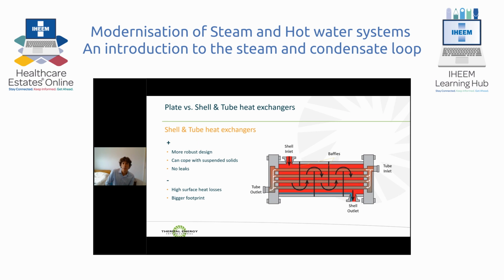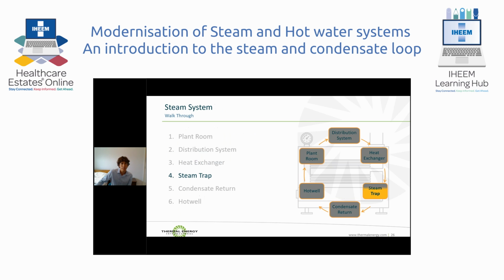Shell and tube heat exchangers are the traditional design. They're very robust, can cope with suspended solids, and are very resistant to leaks. They do have higher heat losses and a bigger footprint within your plant. We now move on to the steam trap.